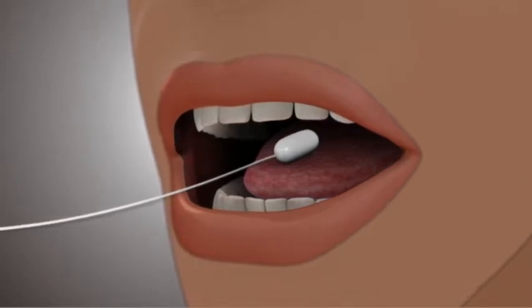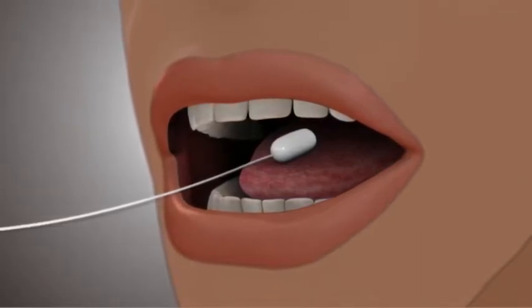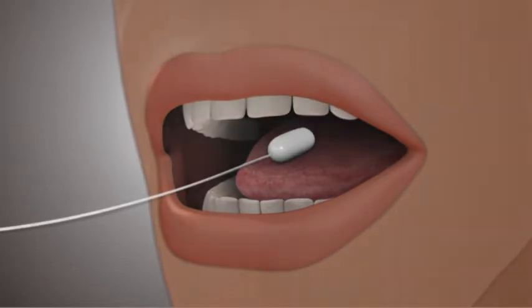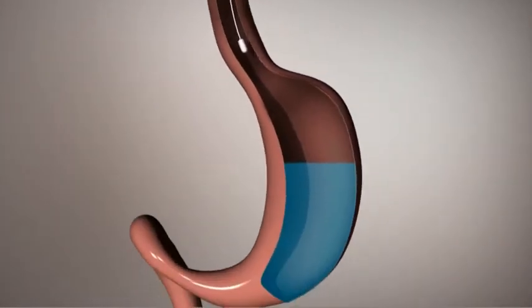The Elipse is packaged into a capsule and attached to a thin, swallowable delivery catheter. The catheter is long enough so that once the capsule is swallowed, the balloon can be filled from outside the mouth.